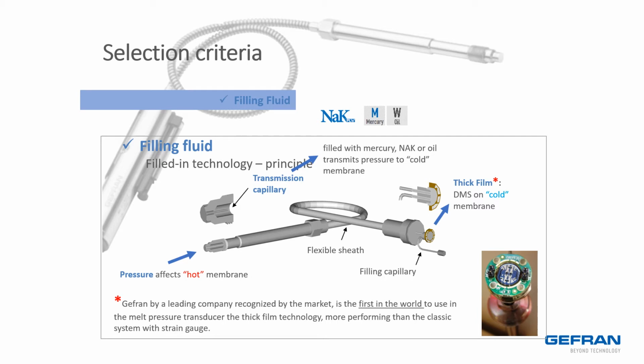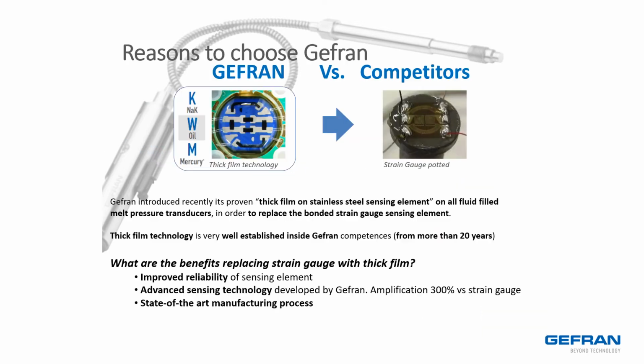Briefly, a melt pressure sensor works like this. Installed correctly, the hot diaphragm deflects as it comes into contact with the medium. The deflection affects a capillary filled with one of a number of substances that then affects the cold diaphragm. Gefran is moving gradually away from strain gauges and toward a design where the cold diaphragm interacts with thick film resistors that are screen printed and arranged onto stainless steel in a Wheatstone bridge configuration. This creates an electrical signal that can be scaled, amplified, and passed to displays and control systems.